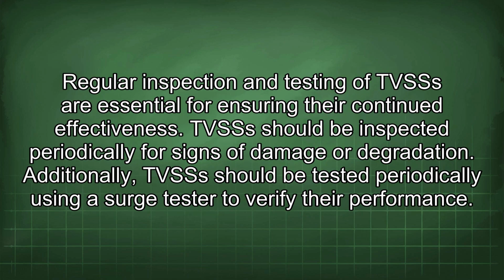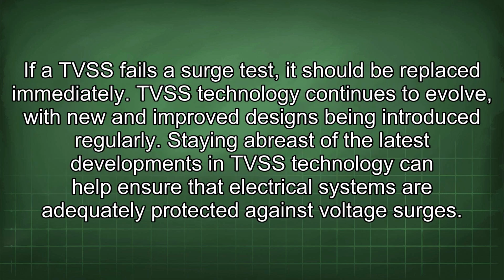Regular inspection and testing of TVSSs are essential for ensuring their continued effectiveness. TVSSs should be inspected periodically for signs of damage or degradation. Additionally, TVSSs should be tested periodically using a surge tester to verify their performance. If a TVSS fails a surge test, it should be replaced immediately.